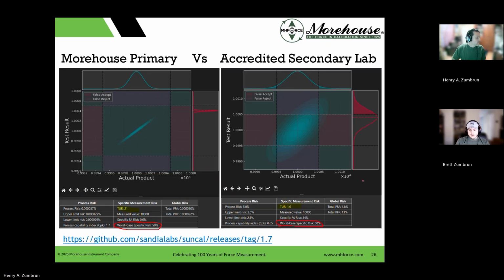Any idea? To be honest, what is that, just a 50% chance that it fails? That's the worst case if I'm using specific risk. What that's telling me is if I run this up to the tolerance limit, half of mine are going to be out at the tolerance limit. And it doesn't matter if my TUR is 21 to 1 or 1 to 1. At that tolerance limit, I have a 50% chance of it being good when it's actually bad, or bad when it's actually good. This is something we typically do not want to run up to the tolerance limits.